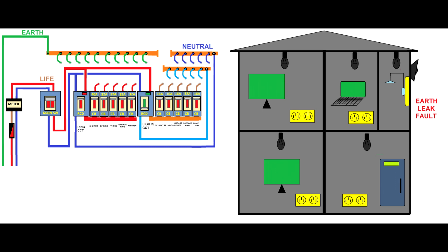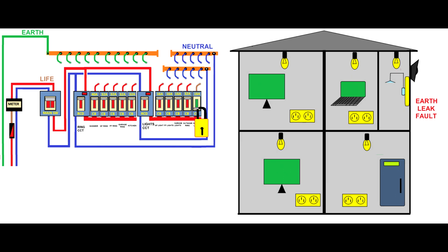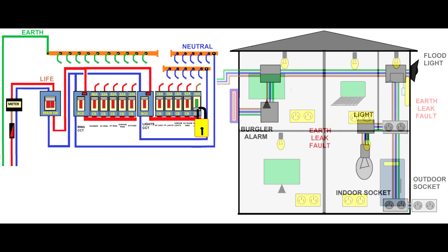So what do you have to do? You have to turn off that circuit breaker and put a padlock on it to make sure no one will activate it, if you don't have time to repair the circuit, of course. And then after you secure that specific circuit, you will reinstate the residual current device. So if you get a call in the middle of the night from someone that has problems, from my perspective, you've been on an emergency job, you make it safe, you reinstate as much as you could, and you finish your job. You give him a quote for the job to be done.